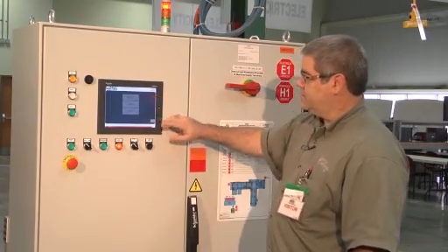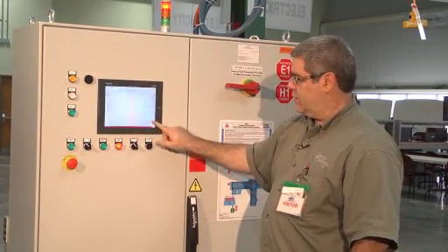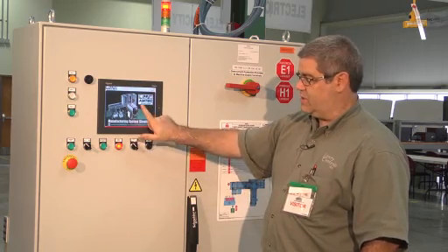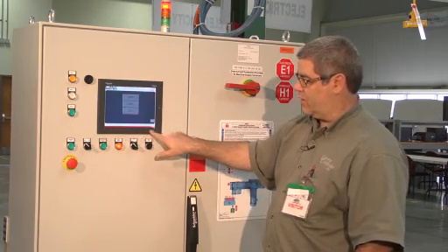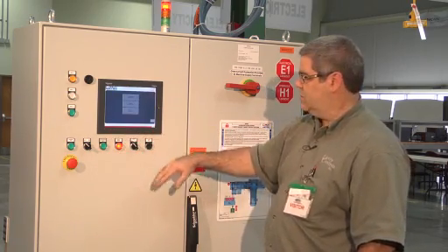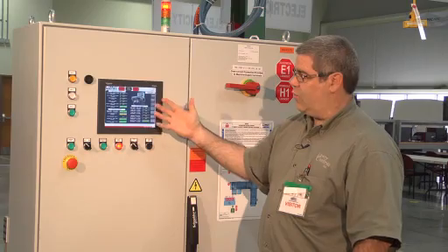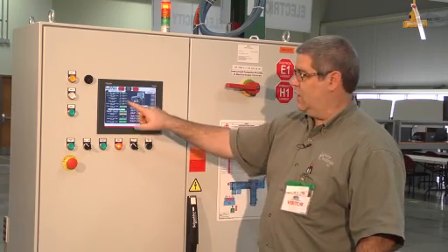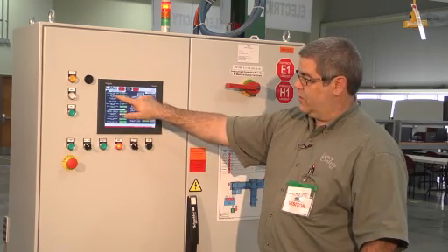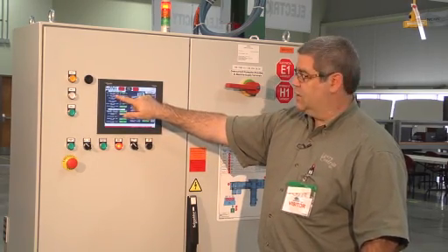On the main screen, it boots up here. You'll come up with a picture. You'll just touch it. You'll notice across the red across the bottom is a scrolling fault message. You go to machine condition, and it tells you the status of what's happening on devices on the machine. And if you'll note here, there's some with device tags that have the identifiers that are in the schematics.